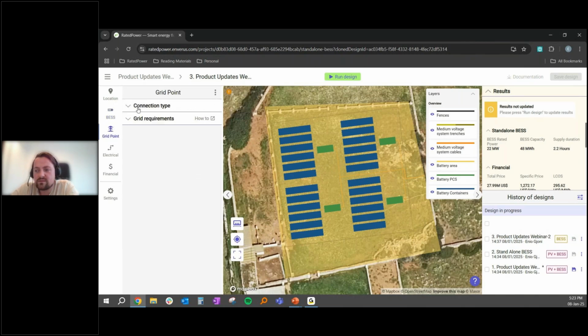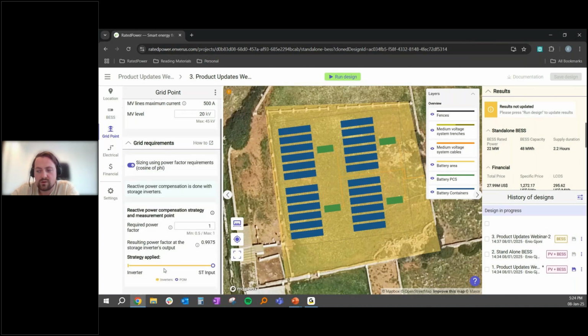In the grid point tab, under connection type, you can choose the MV level the battery will connect to, and include grid requirements such as the required power factor at the point of interconnection, in this case the end part of the battery energy storage system. This will impact the resulting power factor of the storage inverter output.